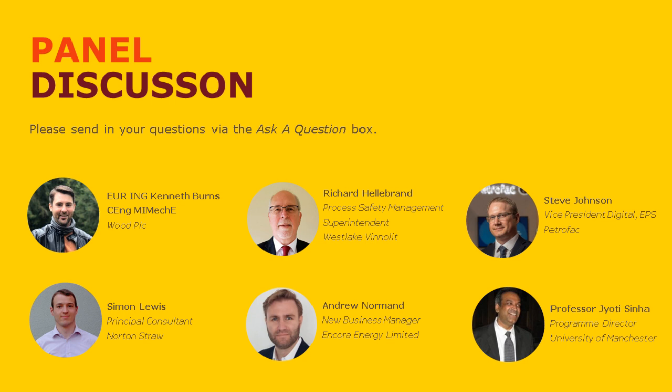It's Richard Hallebrand here. You may not be aware, but actually acoustic emission testing is now being used for complex gearboxes. Sites I work with in Germany have been using TUV, and they did a number of trials on really complex gearboxes, agitators for reactors, elevators, conveyors, and they've been able to come up with a technique that actually analyzes the defects. The advantage of acoustic emission is it works on a different frequency range. You can actually pick up some stuff that really doesn't come out on your normal vibration monitoring. That's another presentation in itself, but it's a relatively early technique, but it's certainly being used in Germany, and if anybody wants the links, I can maybe provide them afterwards.